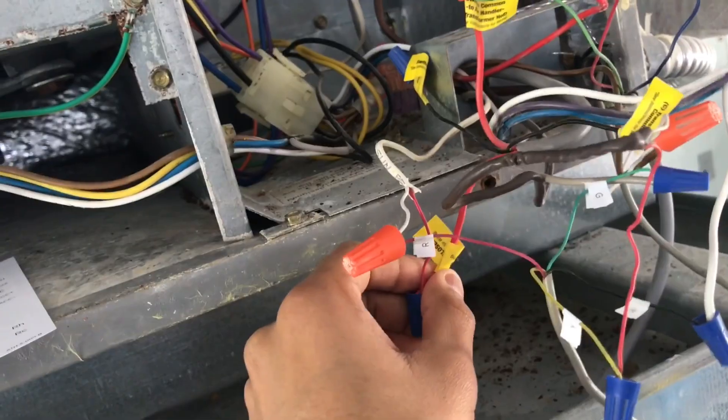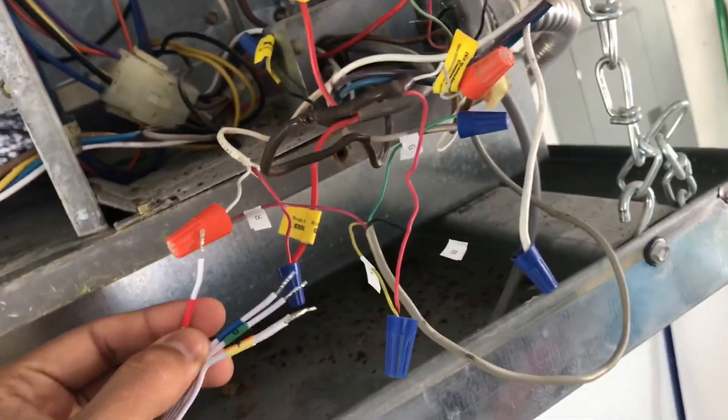If you follow the cables, you have your red coming from the thermostat, but then this taps into smoke detector, then it goes into this other cable that goes into this thing. So it's a closed loop. You can ignore everything else and just replace color with color. You would just install from the PEK connector: the yellow where the yellow is, the white where the white is, the green with the gray as shown on the schematic, and the red with the red, leaving everything exactly how it is.